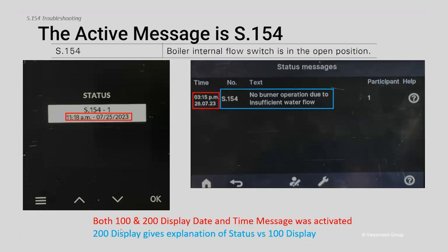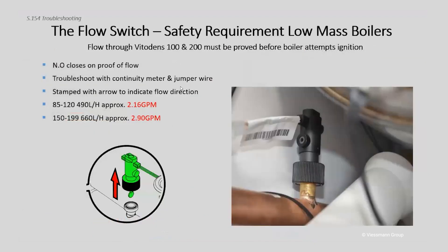With the 200, it gives a better, more full explanation — 'no burner operation due to insufficient water flow.' The primary focus of the S154 is that the flow switch is in the open position when the boiler would expect it to be in the closed position because we've got a call for heat. That would mean the pump has started, which means the flow switch should get the force of the pump's flow pushing that flow switch closed.